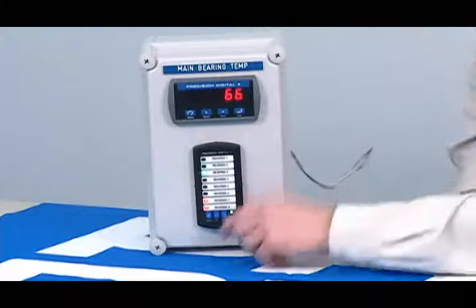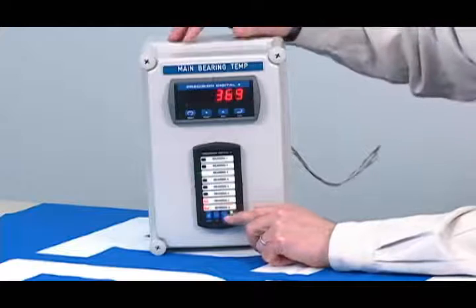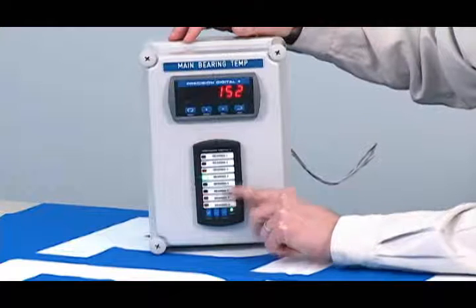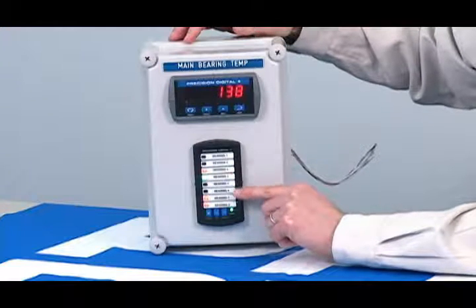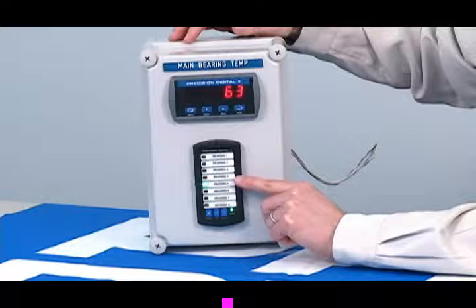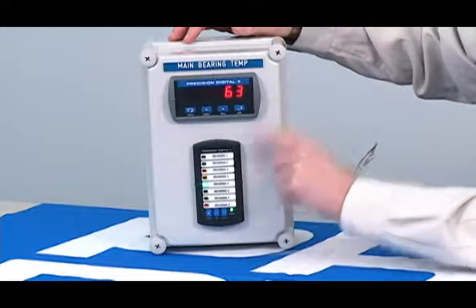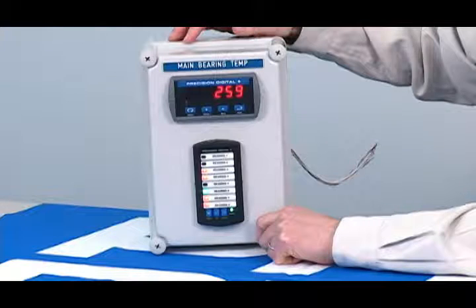And we'll start to get some alarms. So we have bearing number seven, bearing number eight an alarm, bearing number three, and bearing number four. Bearing number five was one of the external ones, so it didn't come on.